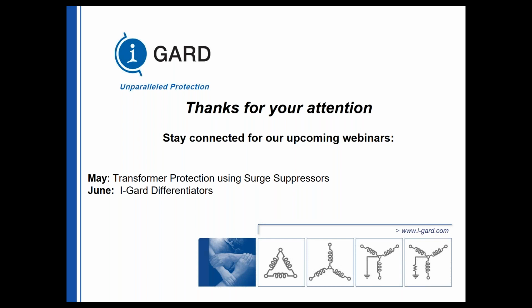Okay, do we have time for one more question? I've got all afternoon. Okay, let's do this one. If the 2 leads per phase are crimped into a ring terminal and the ring terminal comes loose, does it pass the continuity test? Yes, it will. It will pass the continuity test because you have continuous connection between the 2 leads.